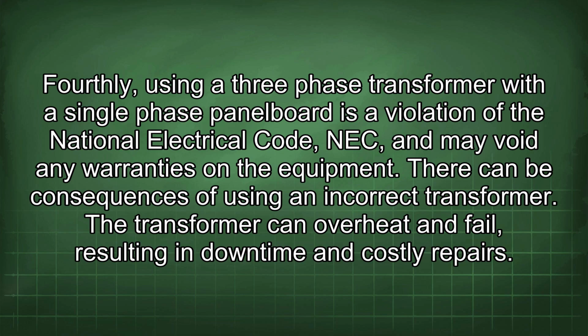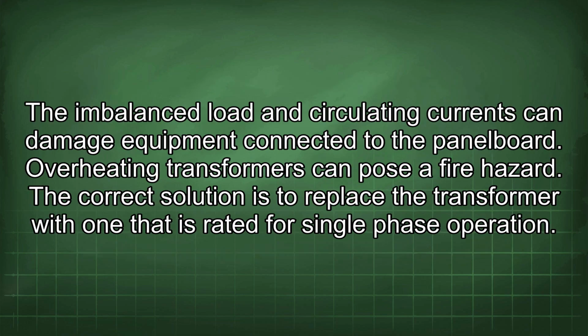There can be consequences of using an incorrect transformer. The transformer can overheat and fail, resulting in downtime and costly repairs. The imbalanced load and circulating currents can damage equipment connected to the panel board. Overheating transformers can pose a fire hazard.